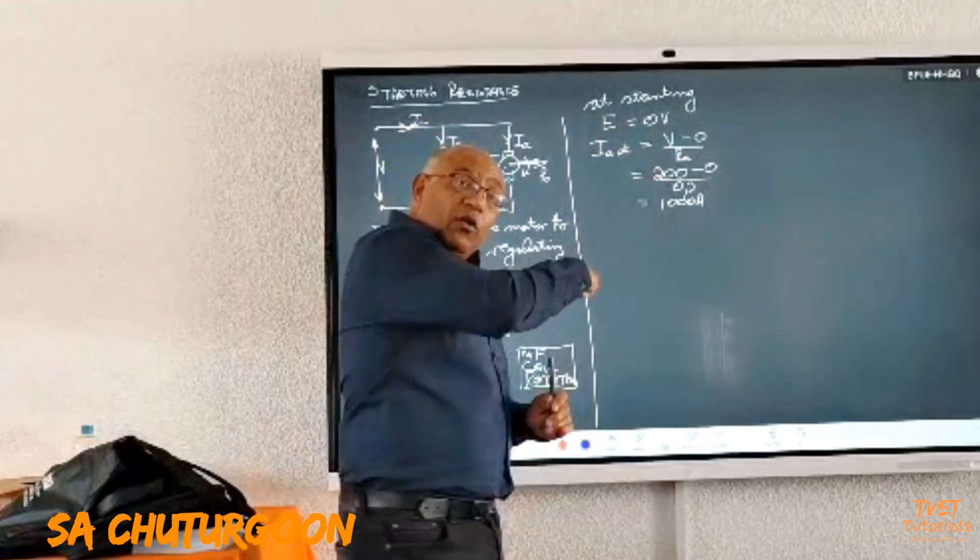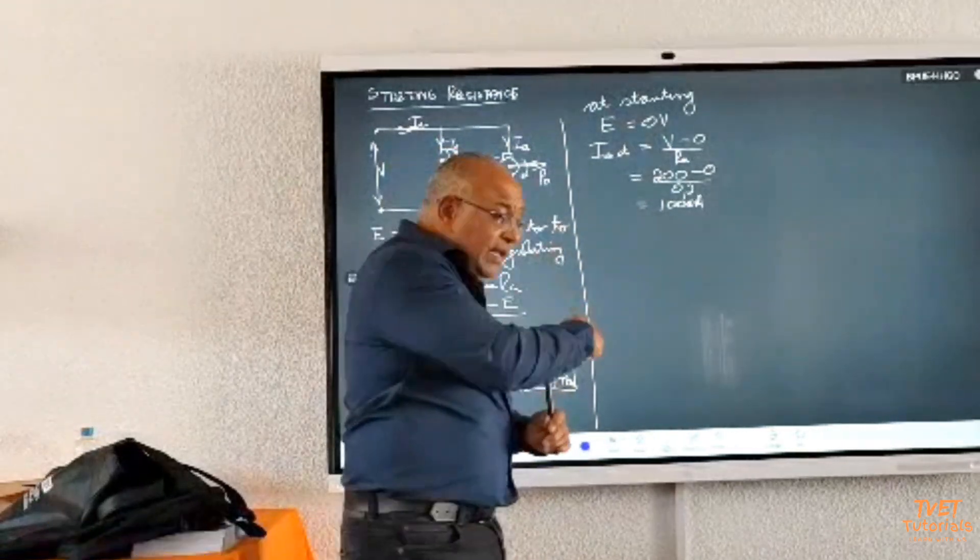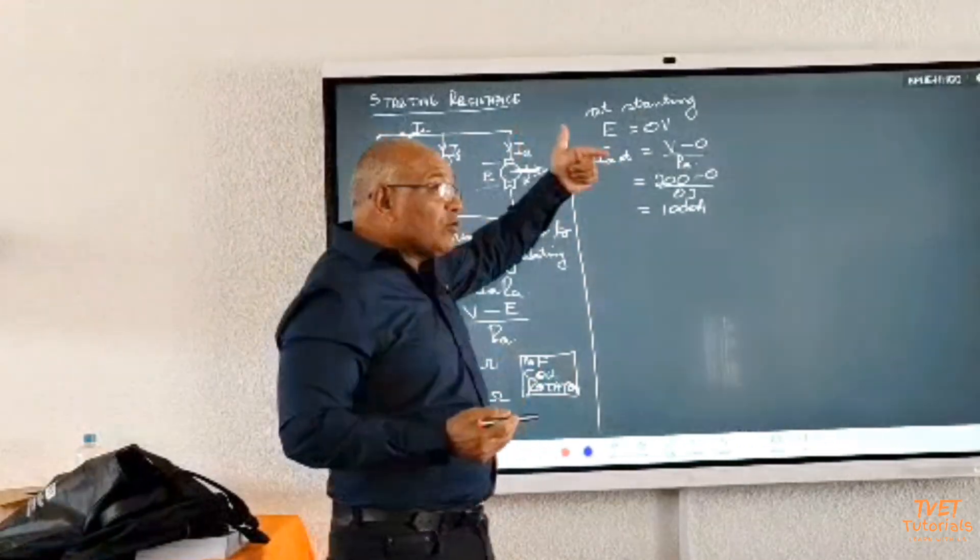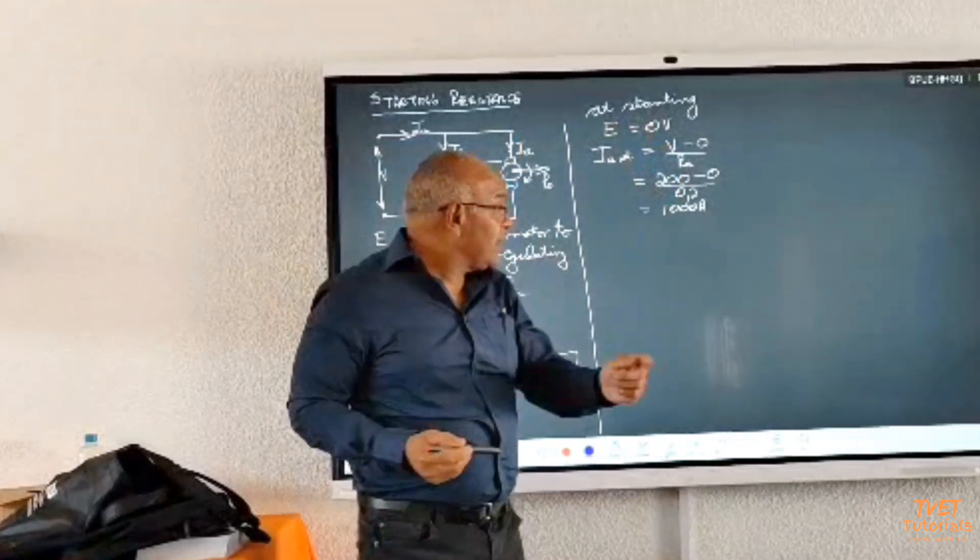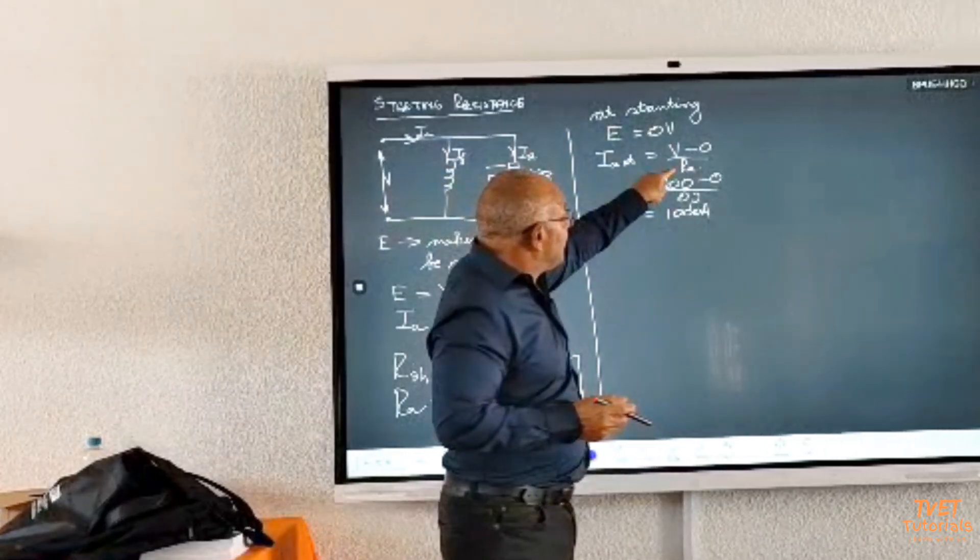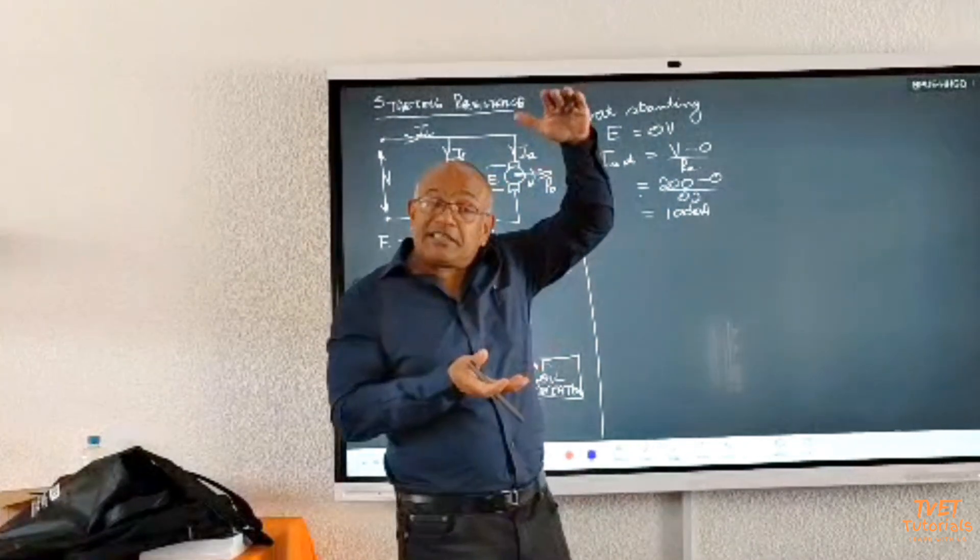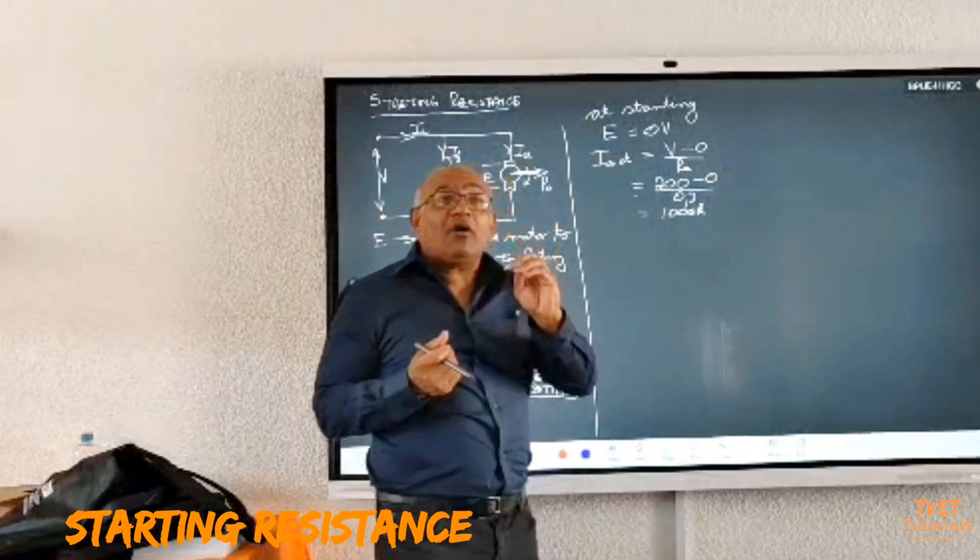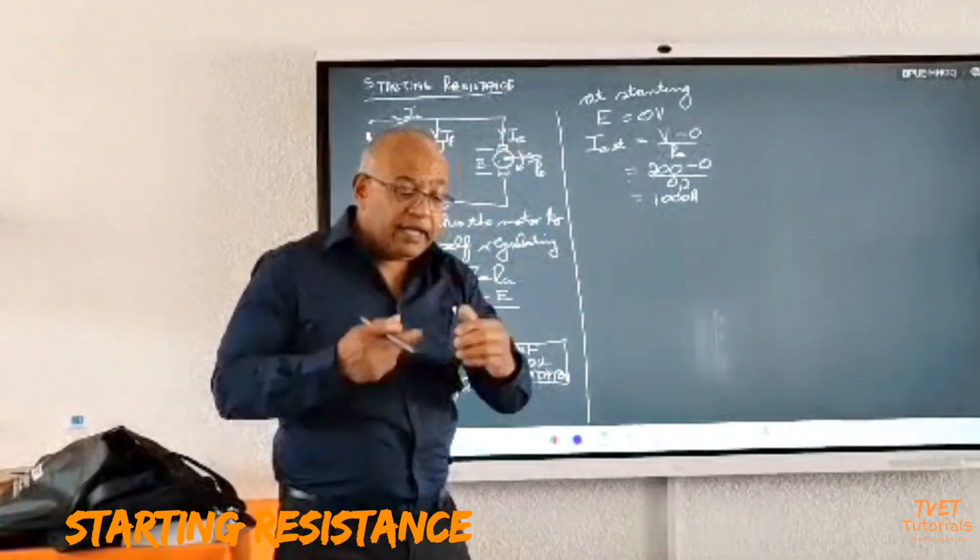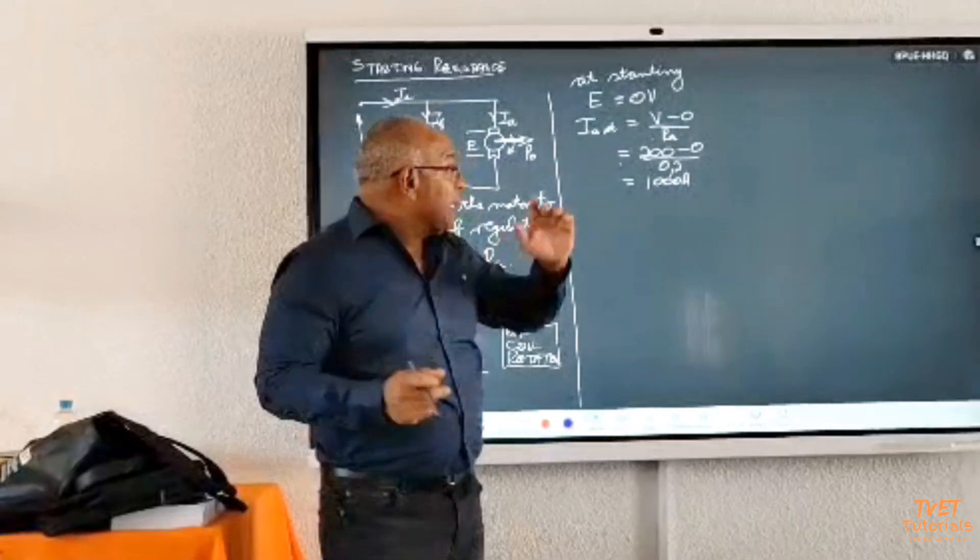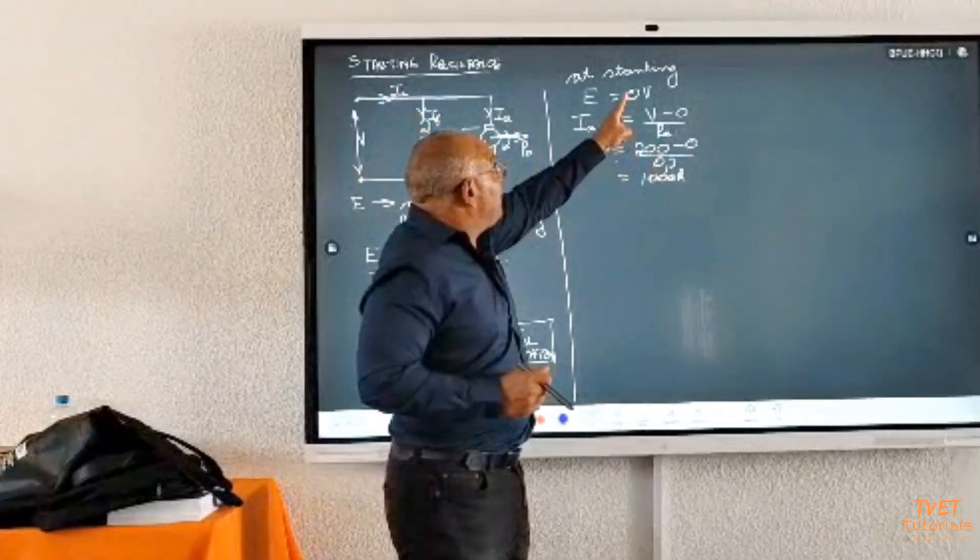We take the spring-loaded starting arm from the off position and bring it to position number one. Current then flows through all the elements, flows through the armature and goes back. What have we done? We have increased the value of the resistance of the armature. What happens to the current? It decreases. Because the current is very small, the motor just begins to rotate.